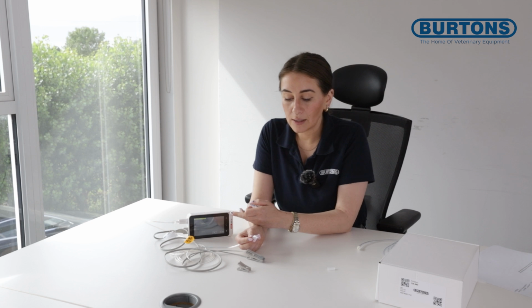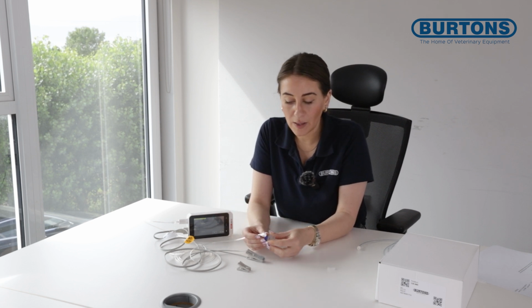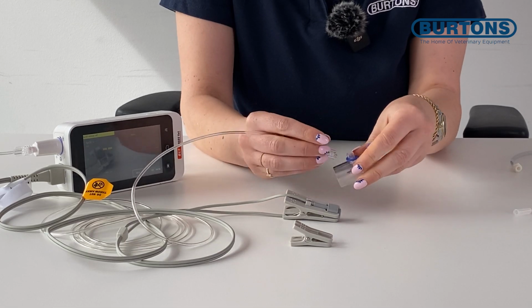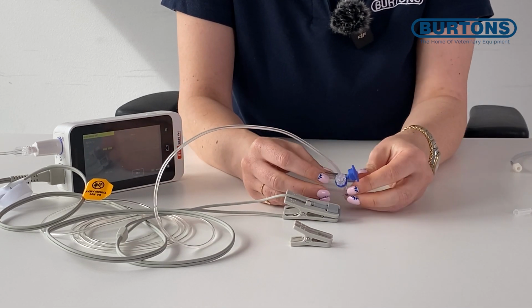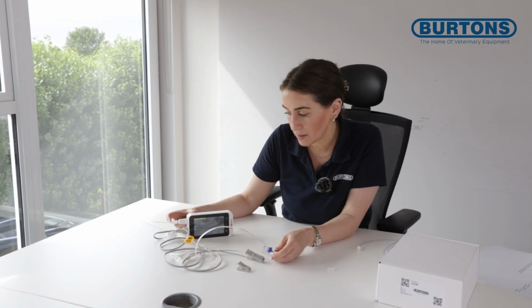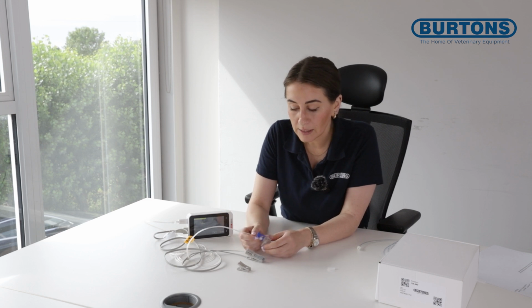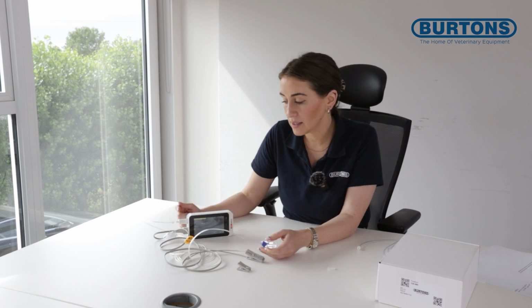So a low ET CO2 with an abnormal trace is our first indicator that there's a leak in the ET tube, and that's where we'd obviously use our cuff inflator to reassess that ET tube and make sure there's no leak anywhere. The adapters can also disconnect from the ET tube, so we want to make sure they're in nice and tight, and certainly that we have this tied nice and tight to the adapter itself. So that's most common. The most common issue is a low end tidal, which is indicating a leak. A leak can also form at this portion here, just as a bend forms over time. When we have unusual graphs or unusual end tidal numbers, that can indicate that there's an issue with the filter, and that's where the filter needs to be replaced.